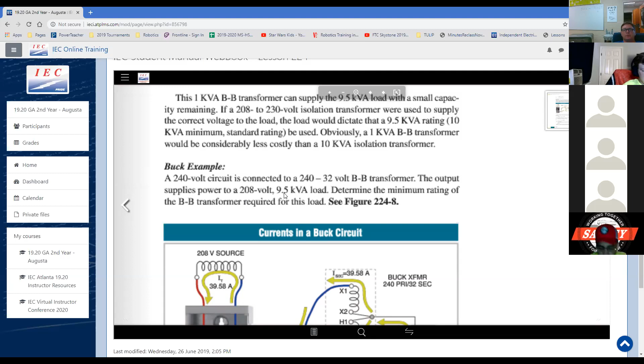It's a motivator. A 240 volt circuit is connected to a 240 by 32 volt buck-boost transformer. The output supplies power to a 208 volt 9.5 kVA load. Determine the minimum rating of the buck-boost transformer. Y'all in the workbook? Yeah, we're in the workbook, 224-7.